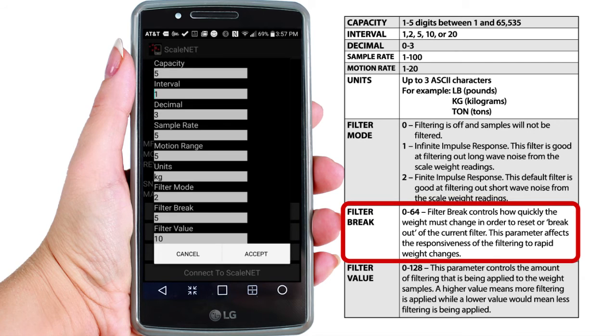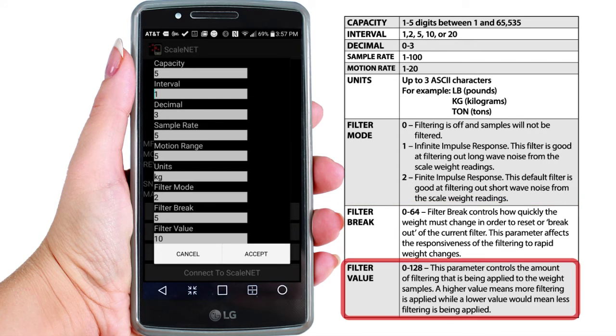The Filter Break controls how quickly the weight must change in order to reset or break out of the current filter. This parameter affects the responsiveness of the filtering to rapid weight changes. The Filter Value parameter controls the amount of filtering that is being applied to the weight samples. A higher value means more filtering is being applied, while a lower value would mean less filtering is being applied.